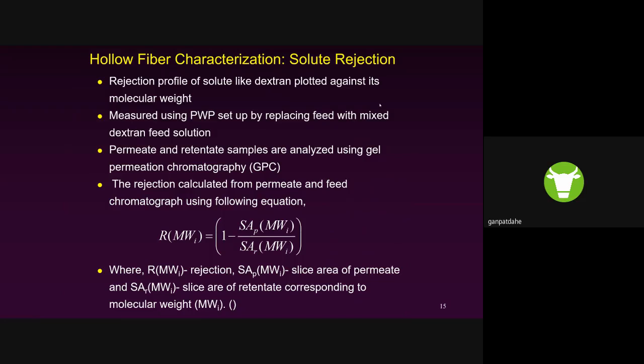In general, they create a mixture of different molecular weight polysaccharides, such as dextran, ranging from 5,000 molecular weight all the way up to a few hundred thousand. This mixture is passed through the lumen of the hollow fiber, and the concentration of dextran is measured from both the permeate and retentate sides. Based on that, one generates the rejection curve.